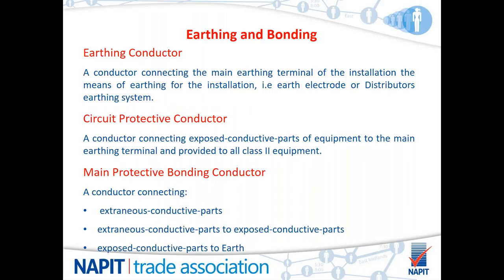Right, so terminology then. These can be found within BS 7671 in Part 2, definitions. An earthing conductor connects the main earthing terminal of the installation to the means of earthing for the installation, i.e. the earth electrode or the distributor's earthing system. A circuit protective conductor is a conductor connecting exposed conductive parts of equipment to the main earthing terminal, and it is not provided to Class 2 equipment. A main protective bonding conductor is a conductor connecting extraneous conductive parts to exposed conductive parts, and exposed conductive parts to earth. And these are all via the MET.